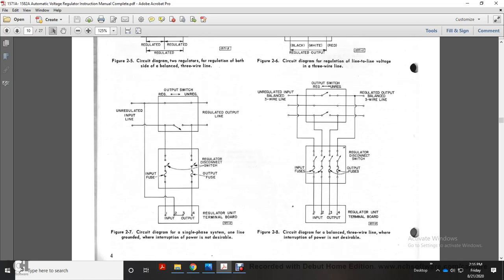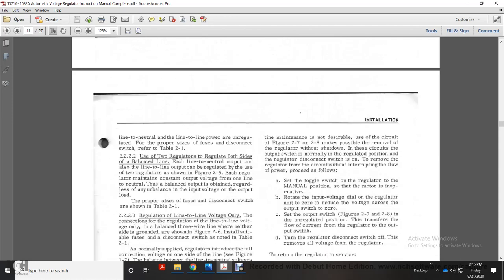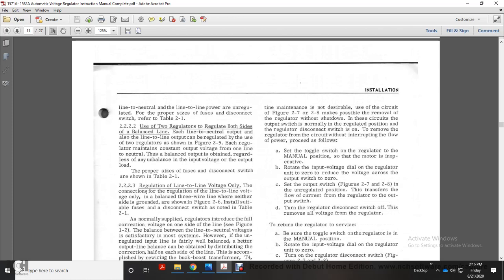Figure 2.7 shows the unregulated input with the output switch, regulator, unregulated, regulated output line, regulator disconnect switch, output fuse, input and output, regulator unit terminal board, circuit diagram for a balanced 3-wire line where the interruption of power is not desirable. Figure 2.8, unregulated input 3-wire line, output regulator, unregulated balance between the regulator and output, balanced 3-wire switch, input fuse. Regulator disconnect switch, output fuses, input output regulator unit terminal board. Alright, your line neutral and the line-to-line power unregulated, for proper size of the fuse and the disconnect switch.